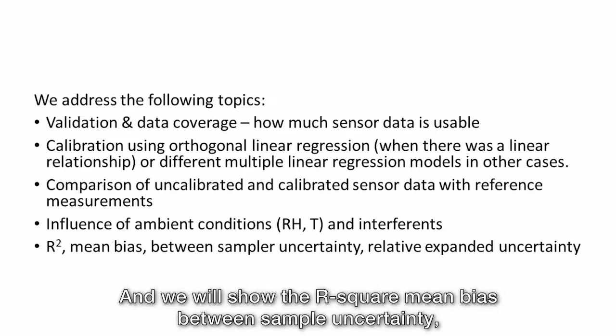So, what is in the reports of the low-cost NO2 and ozone gas sensors? You will find a thorough comparison and statistical analysis of each sensor type and of the 5 individual sensors. We will address the following topics: validation and data coverage, meaning how much sensor data is usable; calibration using orthogonal linear regression when there was a linear relationship, or different multiple linear regression models in other cases; comparison of uncalibrated and calibrated sensor data with reference measurements; the influence of ambient conditions like relative humidity, temperature, and other interference; and we will show the R-square, mean bias, between-sensor uncertainty, and relative expanded uncertainty.